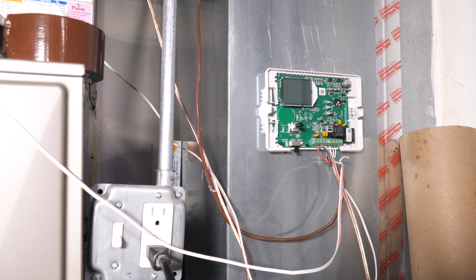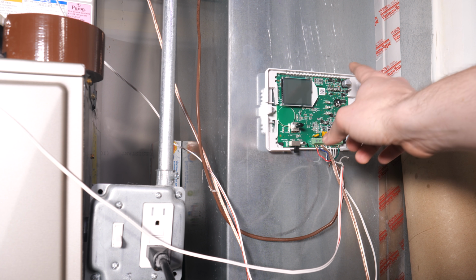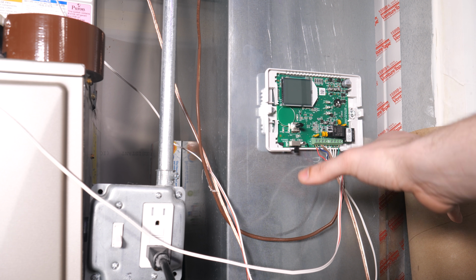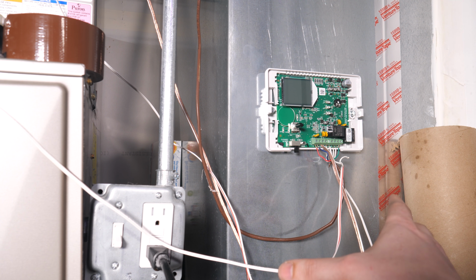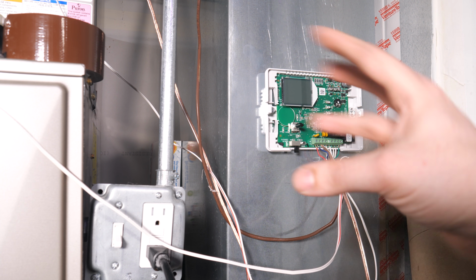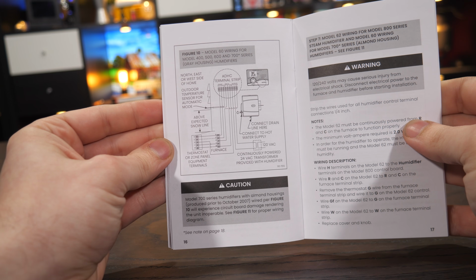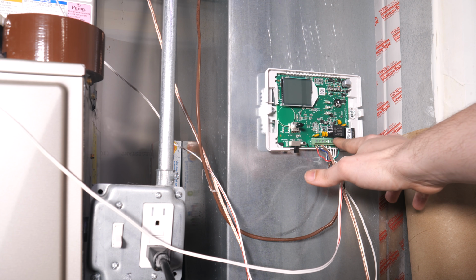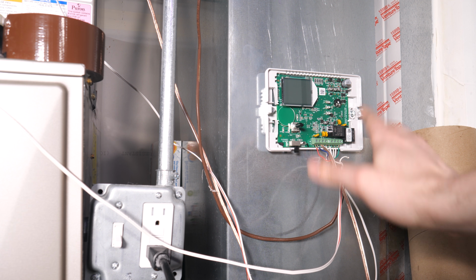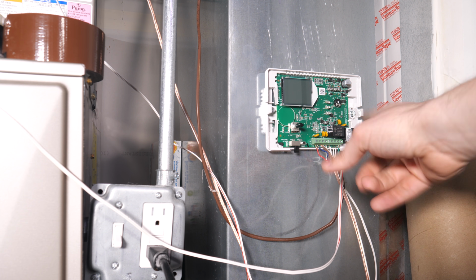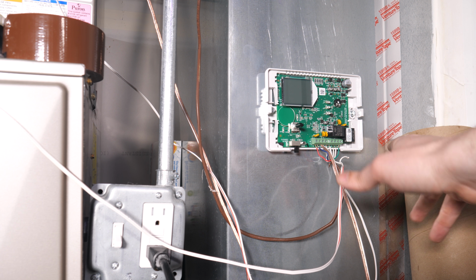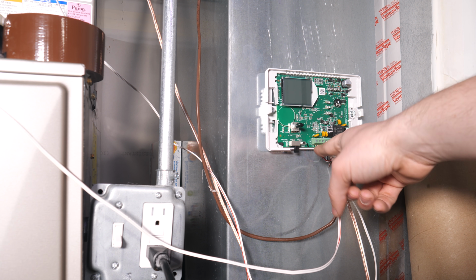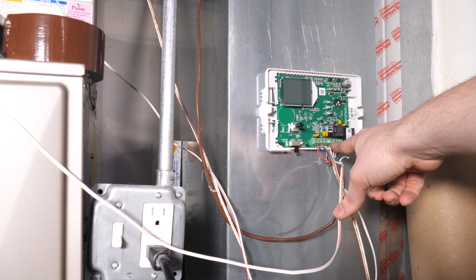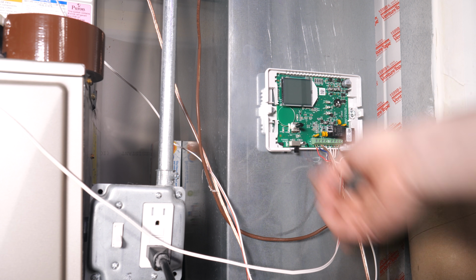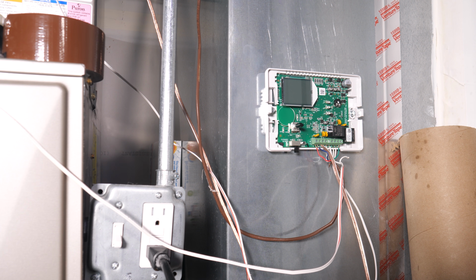And you would think, right, that M stands for manual. The only difference between those models is you get the manual control, the one that I just replaced, or this digital control. But in fact, the 700M gets its 24 volts AC externally from the furnace, and the 700 automatic version has its own 24 volt transformer inside, and all this is doing is bridging these two contacts through this relay. But the manual humidifier needs to get 24 volts AC, which is going to be possible with this. I have to do a little bit of sanity checking to make sure I wire it correctly, but I'm going to have to jump either R or C over to one side of this, and then basically have that relay send 24 volts up to the humidifier like the original control.